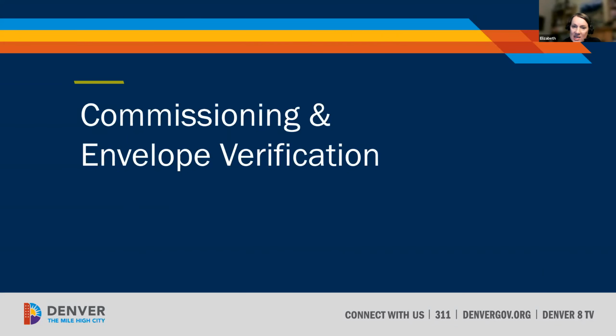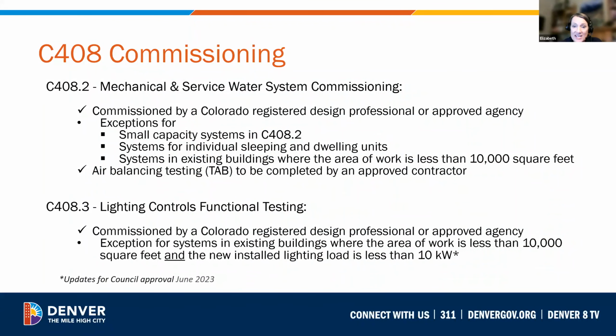All right, we're going to do a quickie overview of commissioning and envelope verification. These requirements are also the same no matter which pathway you choose. When is system commissioning required? Mechanical and service water heating systems must be commissioned when the total mechanical equipment capacity is 480,000 BTUH or more of cooling capacity, or the combined service water heating and space heating capacity is over 600,000 BTUH. Systems that serve individual dwelling units and sleeping units are exempt from that total. Systems in existing buildings where the area of work is less than 10,000 square feet are also exempt.